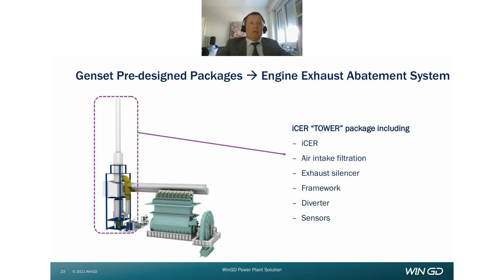Another key item is represented by the ICER, which is the acronym for Intelligent Control by Exhaust Recycling. The purpose of the ICER is twofold. The first one is to reduce the amount of NOx and CO pollutants in the atmosphere without the urea consumption burden. The second one is to enhance the engine internal combustion stability, reducing the fuel consumption and, at the same time, enabling the power plant to operate under a wide ambient temperature range without any derating.